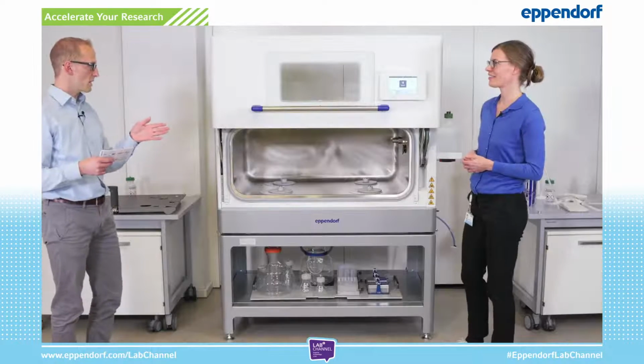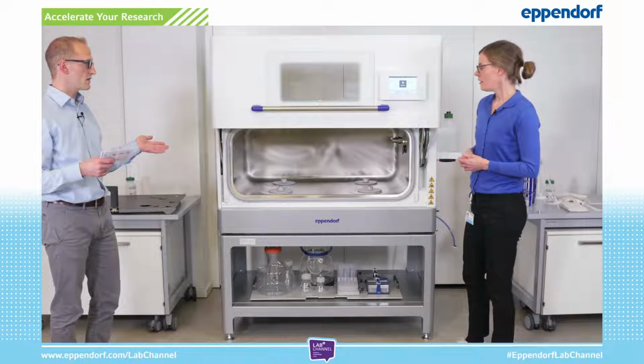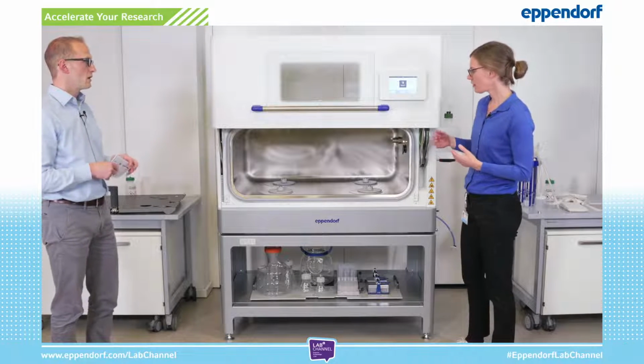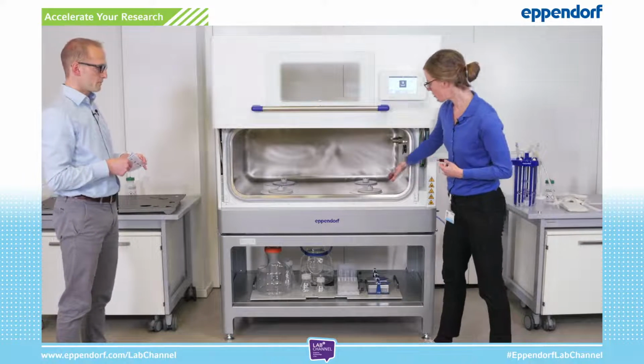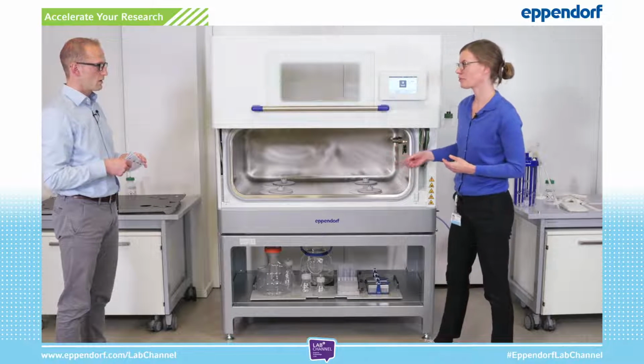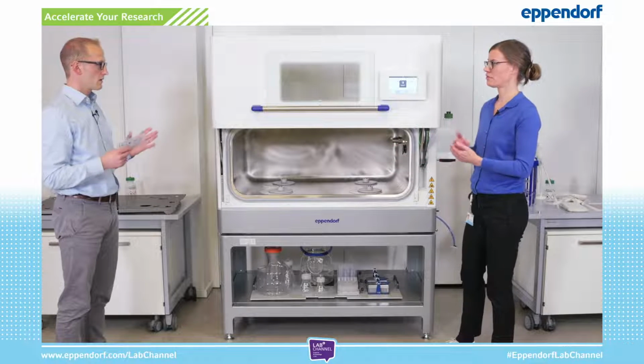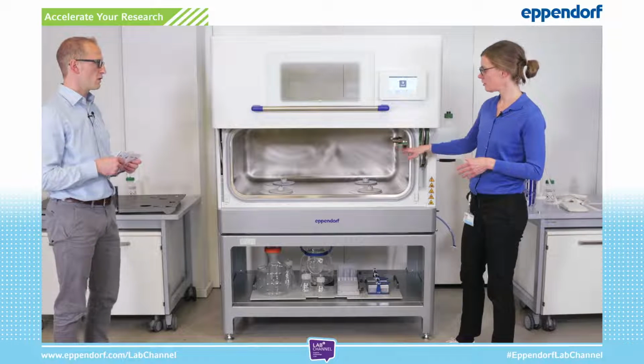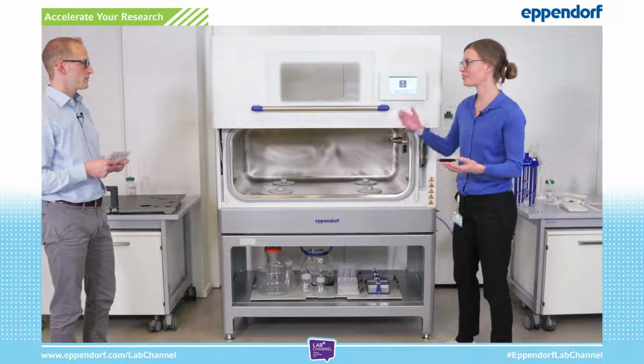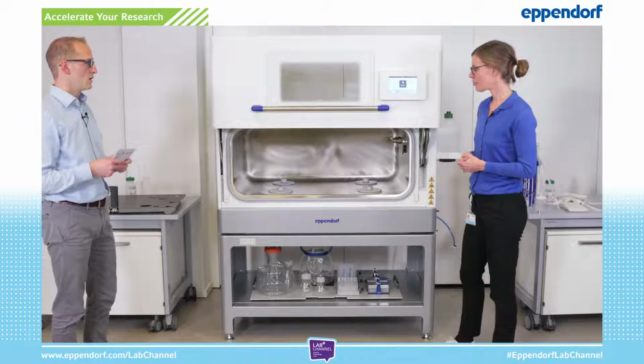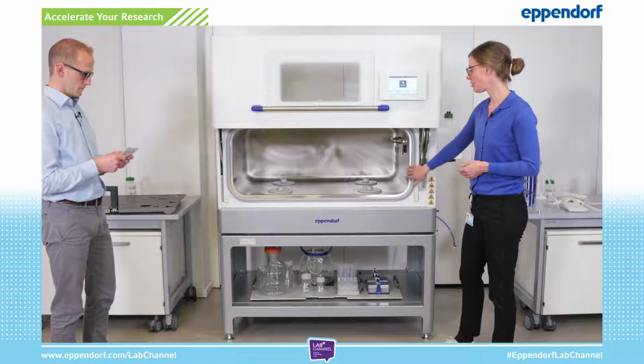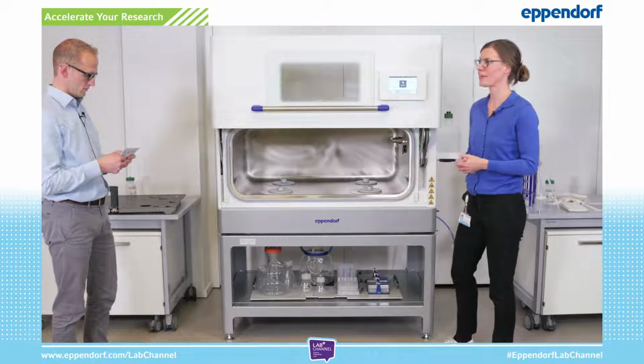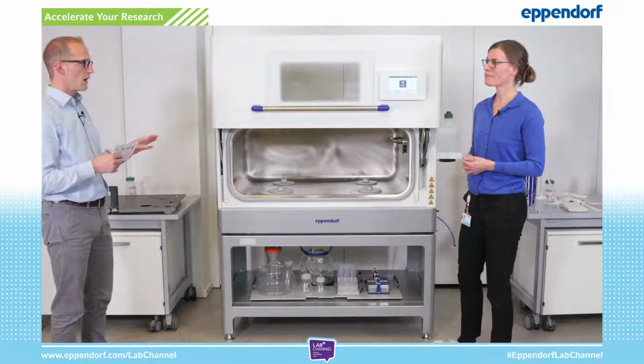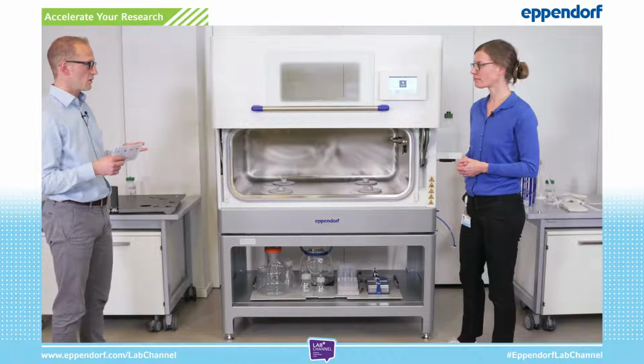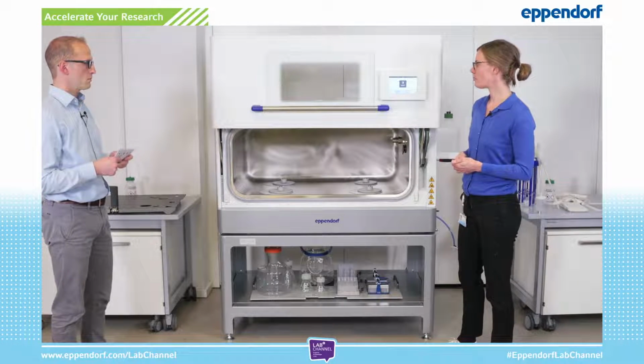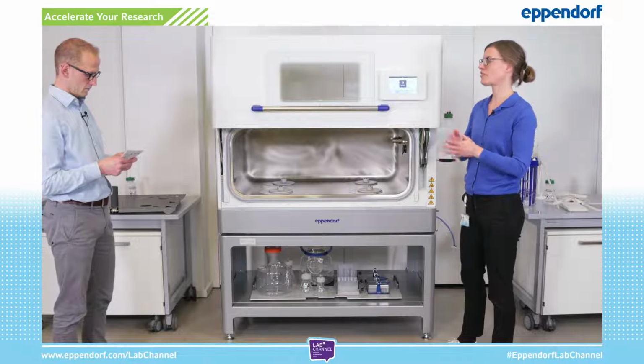Okay, so that's the main difference, I guess, to UV light inside the chamber. Where UV is also very effective, but usually with UV the issue is that you don't have it on all spots. So it's either in the chamber or in the airflow. 180 degrees is on all in-chamber parts. Same with wipe disinfection. Ethanol, of course, is not effective against all contaminants. And the 180 degrees is for 2 hours, right? The holding time? The holding time is 2 hours and the whole procedure is then overnight.